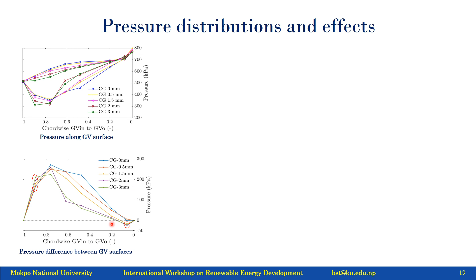There is some strange phenomenon, and I will not discuss it here, but what we can see is that there exists a negative pressure difference with the high clearance gap. This is the high, positive pressure difference from the pressure side to the suction side, and this is the negative pressure difference for the high clearance gap. This pressure difference causes the torque on the guide vane shaft to increase, and it increased quite a lot. Due to the differential pressure and also the additional negative pressure due to the clearance gap, the total guide vane torque increased quite high, up to 28%.